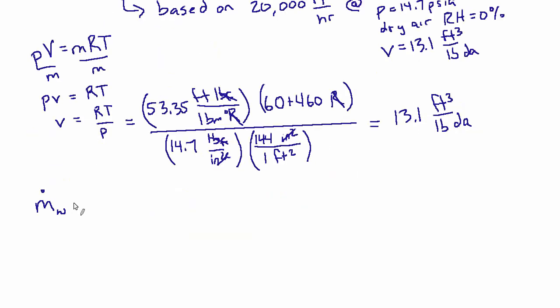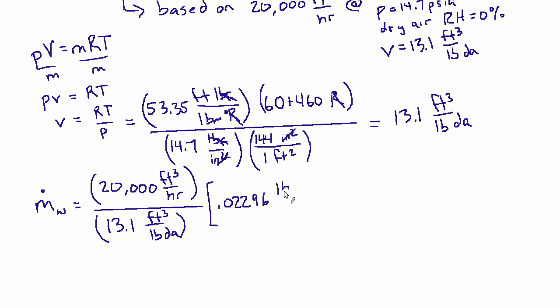So the mass flow rate of water is that volume flow rate, 20,000 cubic feet per hour, divided by the specific volume to get it to be a mass flow rate, 13.1 cubic feet per pound. And then the difference between the humidity ratios: 0.02296 pounds of water per pound of dry air at state two, minus 0.00484 pounds of water per pound of dry air at state three after that cooling process.